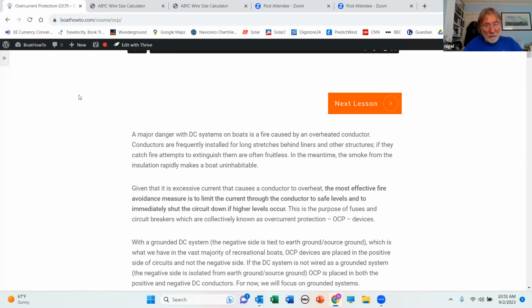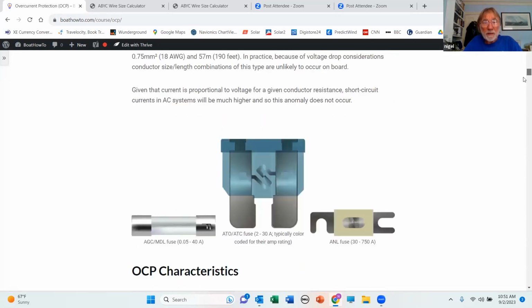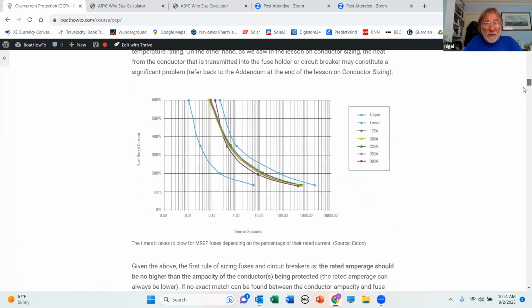So then with fuses, they have different tripping and blowing rates. I think I actually have a couple of slides on the same with circuit breakers. This is a fuse. So typically speaking, in a standard ambient temperature, which is like 77 degrees Fahrenheit, the fuse or circuit breaker will actually not blow or trip until 130% of its current rating. So if it's a 100 amp fuse at 77 degrees Fahrenheit, it's not going to blow until you put 130 amps through it. So there's a fair amount of margin built in there.